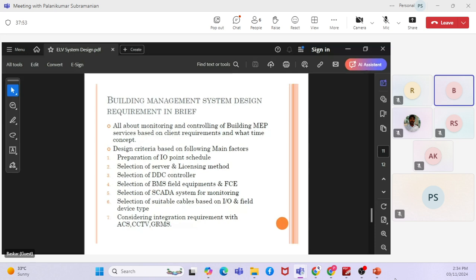The selection of the DDC controller also plays a very important role here. When we select the DDC controllers, we should not select very few controllers or too many controllers, as that will also make an under or overcost. So choosing the DDC controllers is mainly based on location. We need to segregate the locations, and based on the locations we can make a cumulative IO point schedule for each DDC. Then we select the controllers based on the total IO point schedules. When we talk about IO points, there are different types of IO points. I will explain in brief at a later stage.